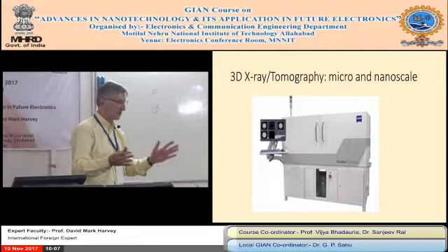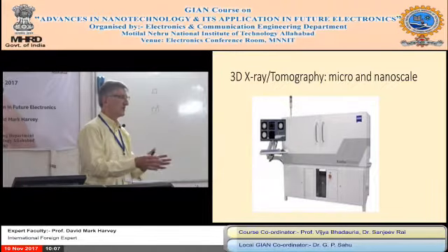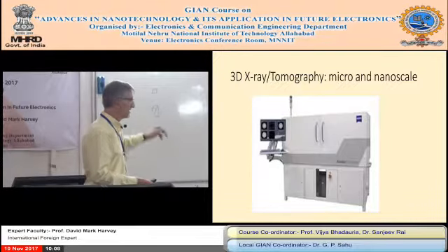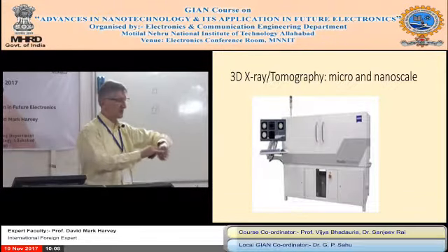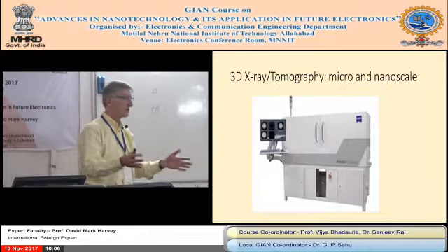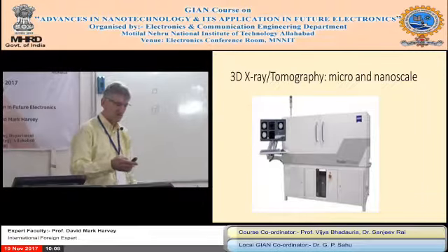And if you want to do a circuit board, you can't fit a whole circuit board into a chamber of the highest resolution. You have to cut it. You can only do 50 nanometers on a small sample, say maybe as big as your thumbnail. If you want to do a bigger sample, the resolution's not as good. So there's drawbacks in all these things, so it's a bit of know-how how to use it.